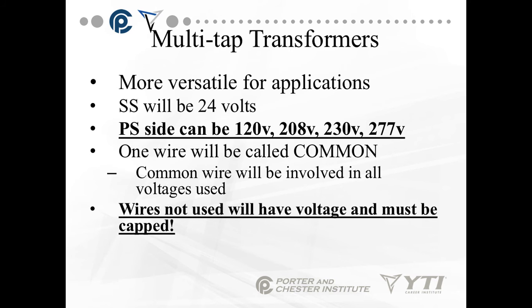Now, there's also a thing called multi-tap transformers. They're more versatile for applications. The secondary side will be 24 volts, but the primary side can be 120 volts, can be 208 volts, can be 230 volts, can be 277 volts. One wire is going to be called a common. Most often, by the way, that wire is going to be white. The common wire will be involved in all voltages used. Any wire you're not using will have voltage and must be individually capped. Don't throw them under one wire nut.